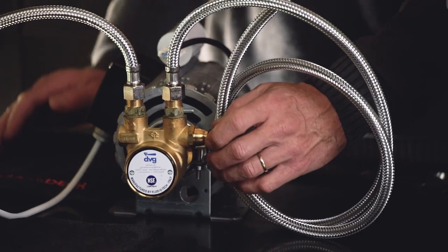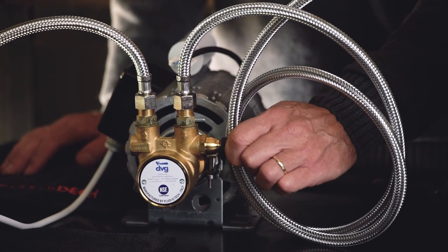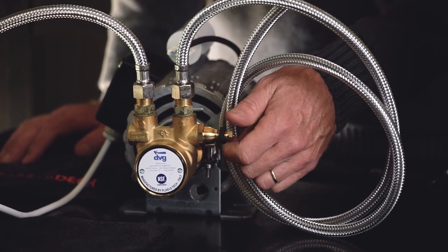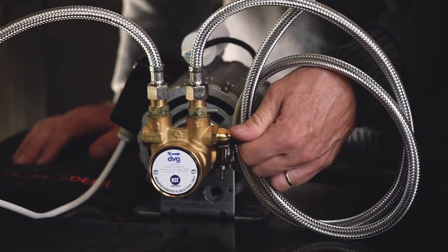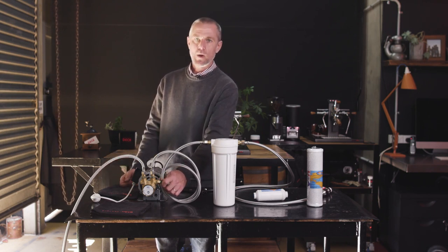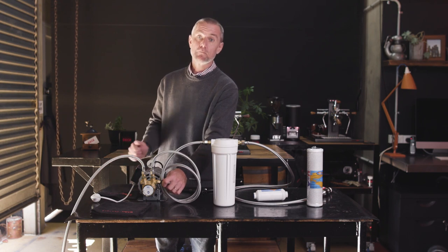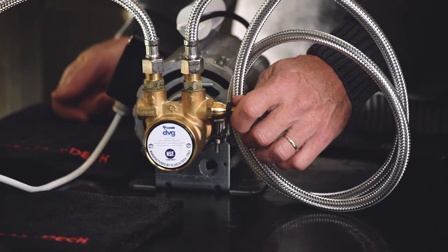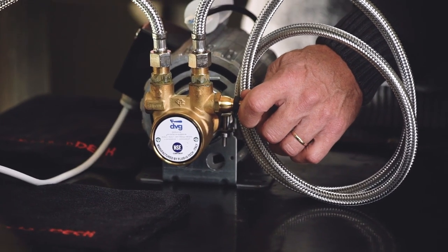So this is a little adjusting nut here. The further out you set that, the lower the pressure. The more you wind it in, the higher the pressure. But ideally, the optimum pressure is nine bar. And that's when loaded with a blind filter in the basket, then I would adjust that to show nine bar.